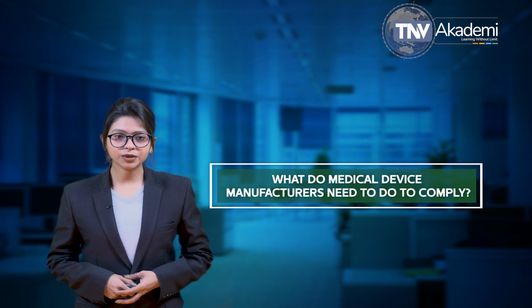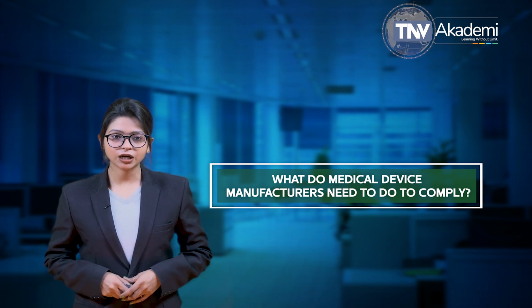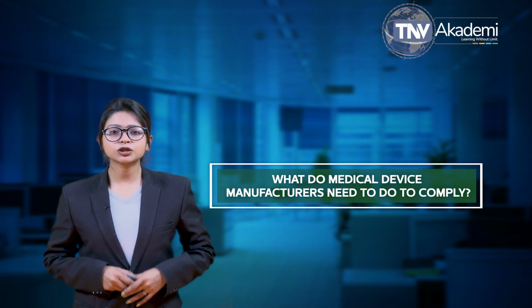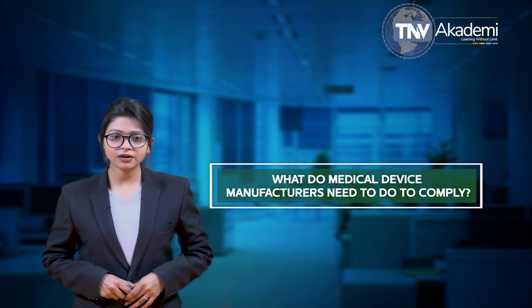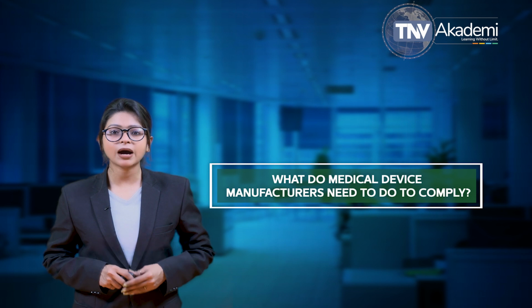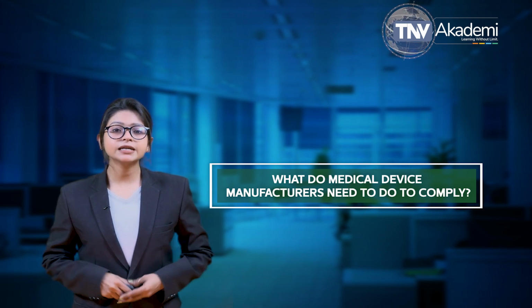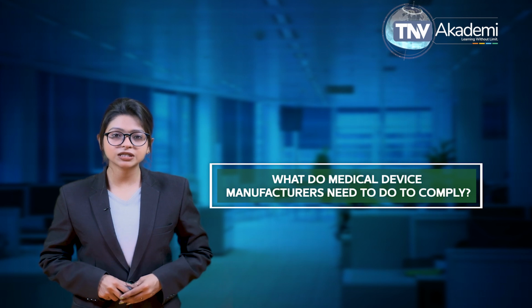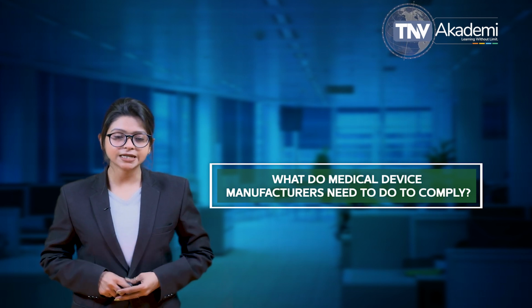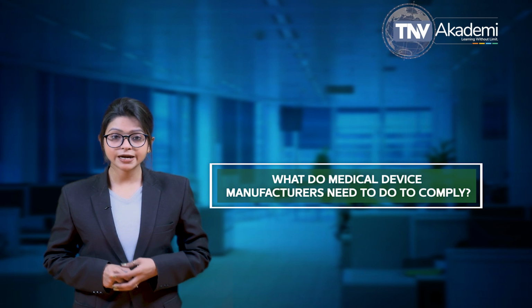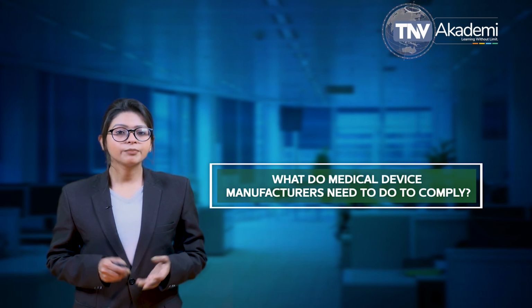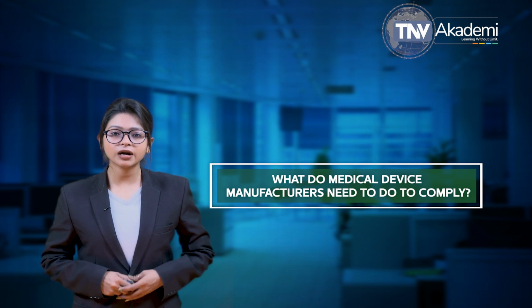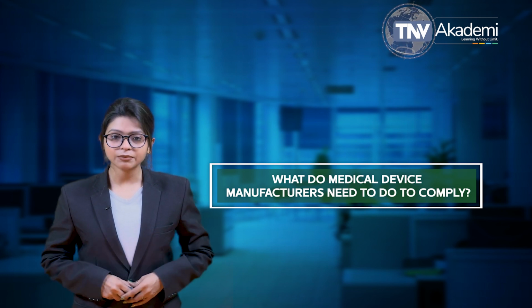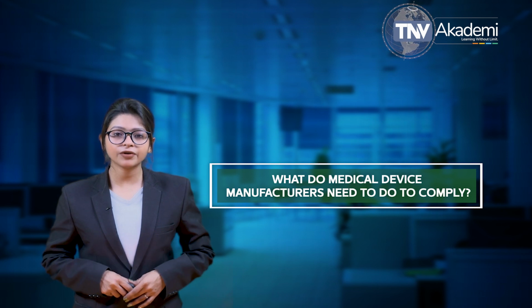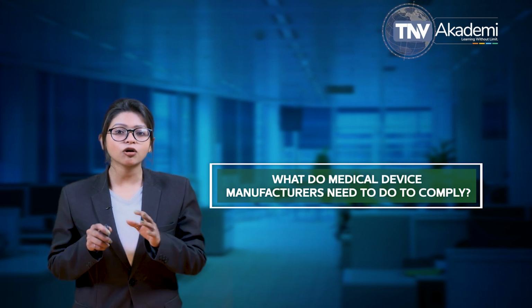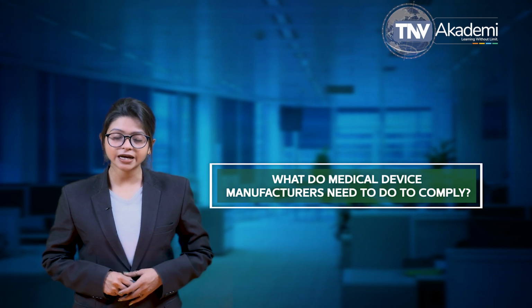Once all of the data have been gathered, ISO 10993-1 requires a qualified individual, usually a toxicologist, to review the data and develop a weight of evidence argument called a biological evaluation. Historically, device manufacturers have been able to reach successful submission with biocompatibility testing alone. However, more often than not, this is no longer the case. Beginning with biocompatibility testing is no longer a best practice, because complete chemical characterization followed by a favorable toxicological risk assessment can often address several biocompatibility endpoints.